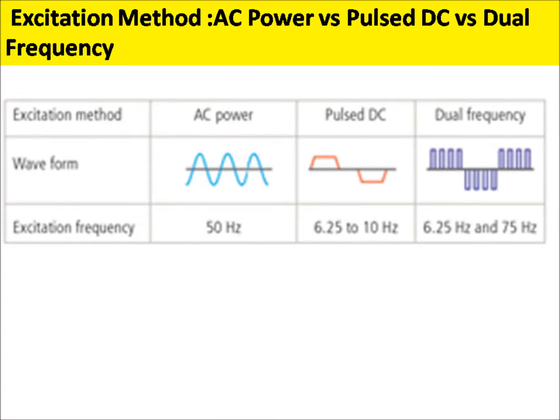As new power supply circuits developed, instrumentation designers had more options available to try different excitation frequencies. This led to adjustable sensors where a user could choose the best frequency for the application. If the process is noisy with slurries or flow rates change rapidly, the user chooses a high frequency. For an intermittent process, such as a batch application with periods when flow stops, the user chooses the low frequency.